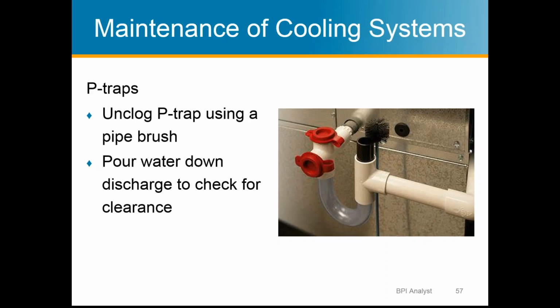And the P-trap is just what you see there, but the low portion should be full of water, and that blocks air from escaping from the evaporator coil. So it helps stop air leaks through the evap coil, which is part of the reason why we have a P-trap at all. And also, if any debris were to come in, that's where it would stop, so it's easier to clean out. So you just want to make sure they're clean.